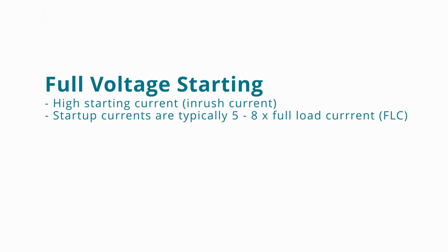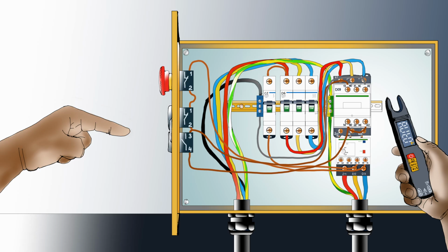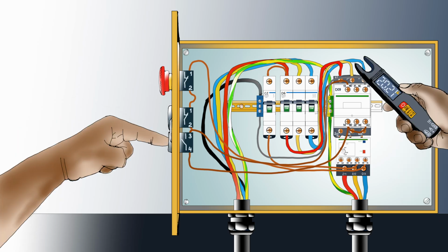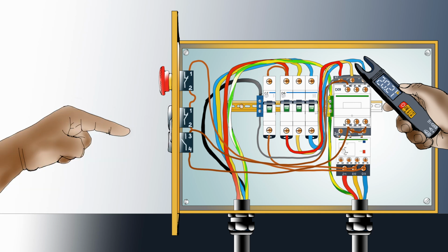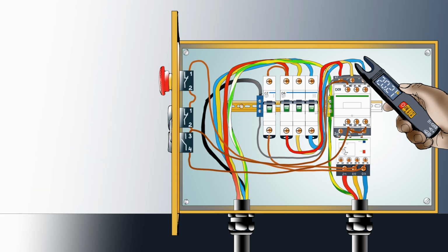Full voltage starting results in high starting currents called inrush current. This can be as much as 5 to 8 times the full load current of an induction motor. For example, a 2.2 kilowatt, 3 horsepower motor with a full load current of 4.5 amps could draw up to 20 amps or even 36 amps at startup. That's a bit too much considering the motor draws less than 4.5 amps in normal operation.